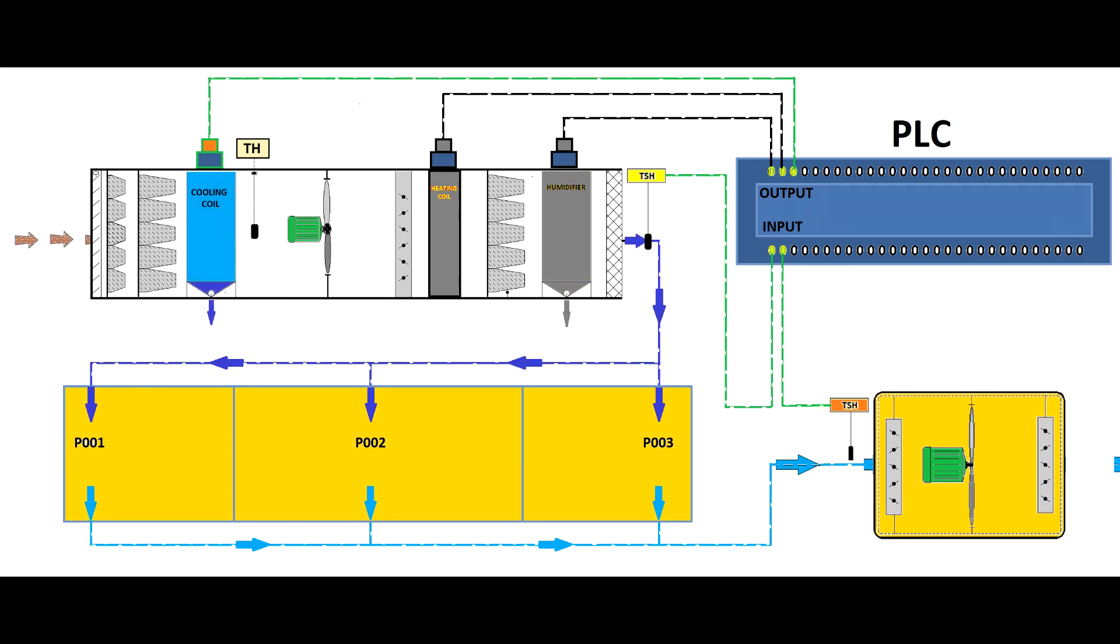This is another scenario. In this case, you run only the cooling heat exchanger. And as I said, this heat exchanger can run now for dehumidification, because as you know, if you drop the temperature of the heat exchanger below the dew point, you will remove moisture from the air. Or maybe you only want to cool the air.